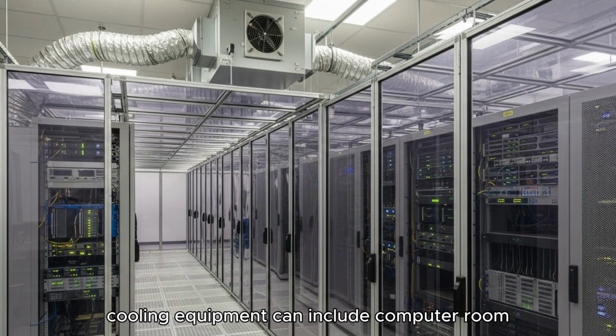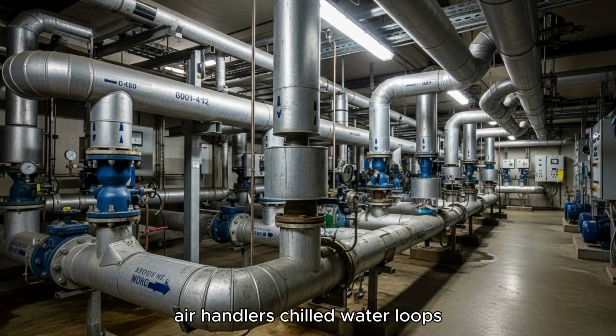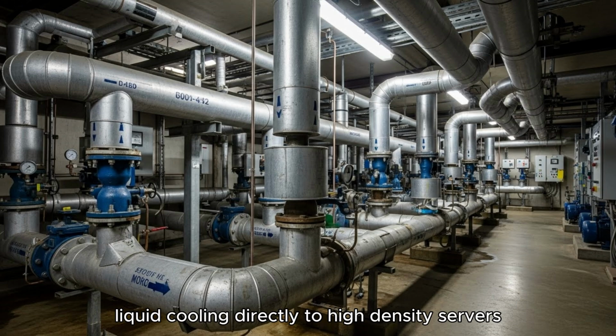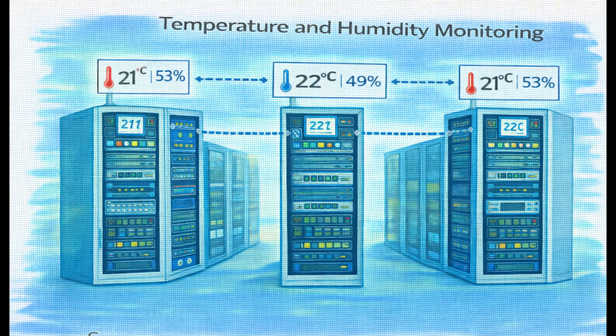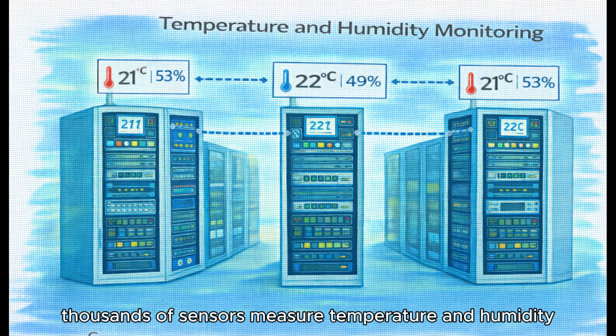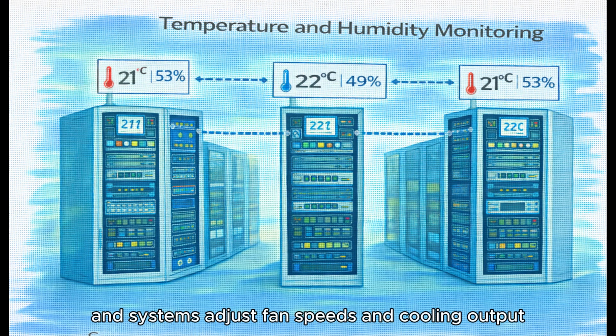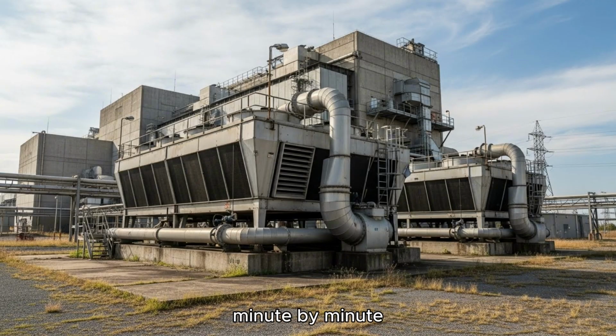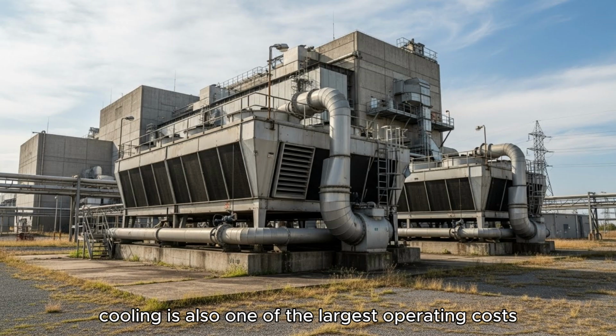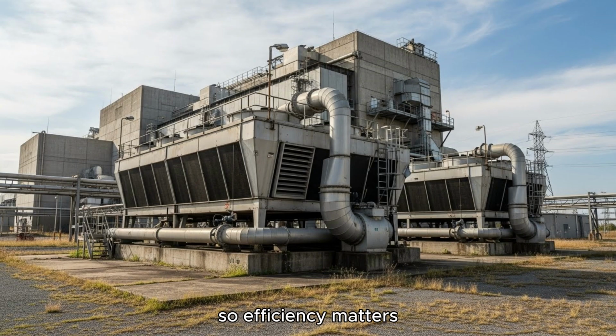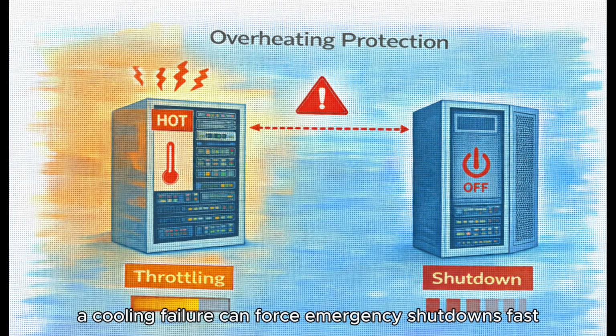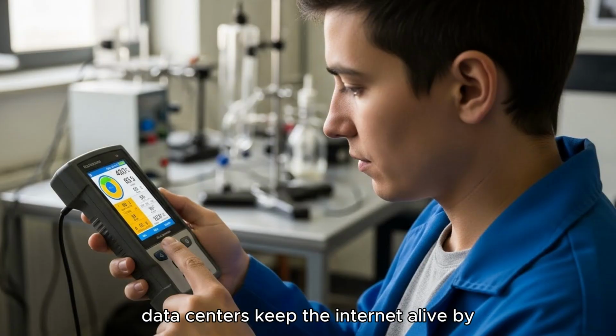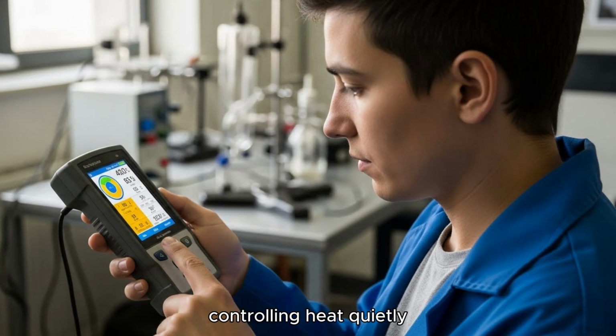Cooling equipment can include computer room air handlers, chilled water loops, cooling towers, and in some cases, liquid cooling directly to high-density servers. Thousands of sensors measure temperature and humidity, and systems adjust fan speeds and cooling output minute by minute. Cooling is also one of the largest operating costs, so efficiency matters. A cooling failure can force emergency shutdowns fast. Data centers keep the internet alive by controlling heat, quietly, continuously, and with backup capacity.